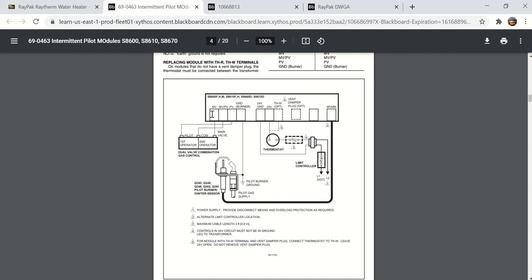Now, on most of these or all of these ignition controls we're going to look at, the main valve and pilot valve are powered with these three terminals. Here's the ground that goes to the pilot burner. Here's the high voltage spark terminal. And here is the 24 volt ground, 24 volt hot. That's the power that comes from the transformer.